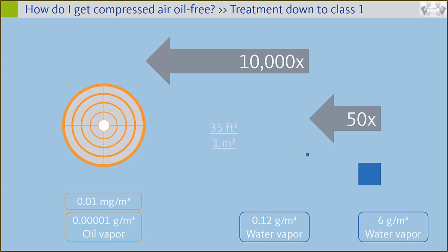Yeah, Bernd, there are two of them actually, both regarding the BEKOCAT. All right. I remember the point where you showed the benefits of the BEKOCAT, or the positive points, and one of them was it is load independent. And I also remember that you said that it can go down to 20% of the nominal volume flow, so minimum 20% of the nominal volume flow that it can work. So the question now is, does it need constant volume flow, or is volume flow with fast changes also possible? So without constant volume flow and fast changes, would it still work?